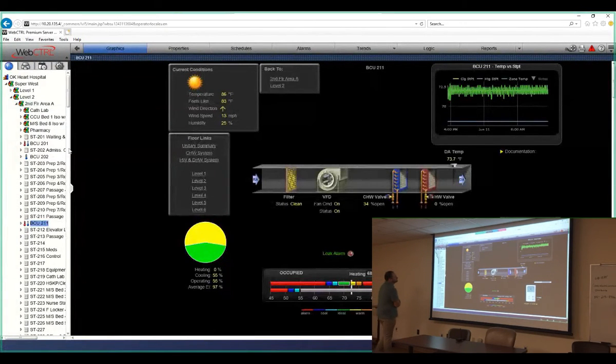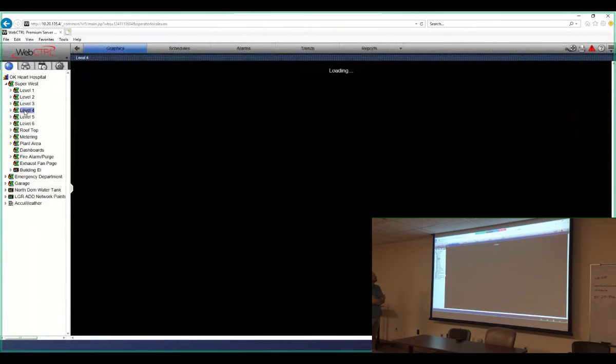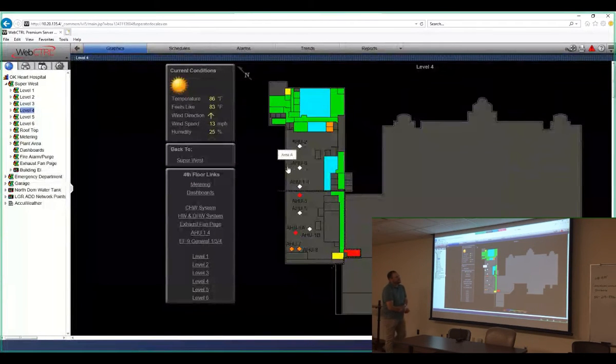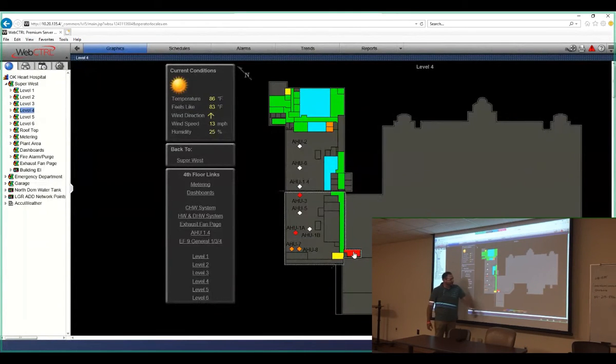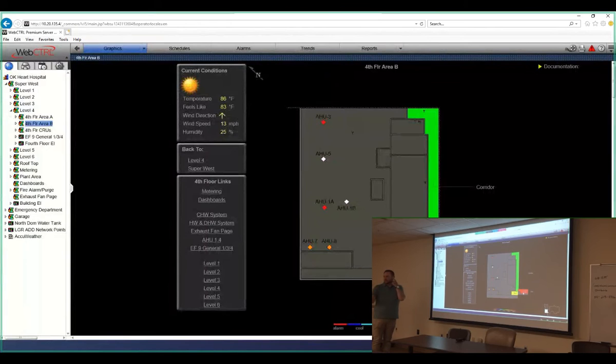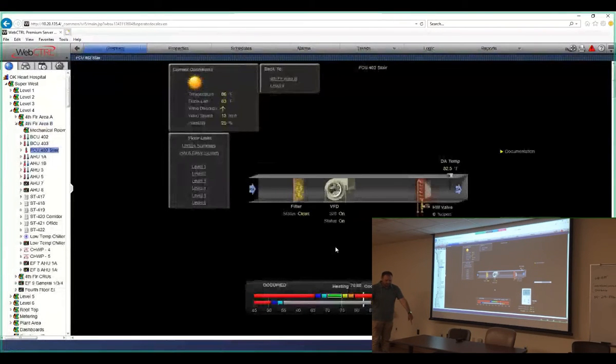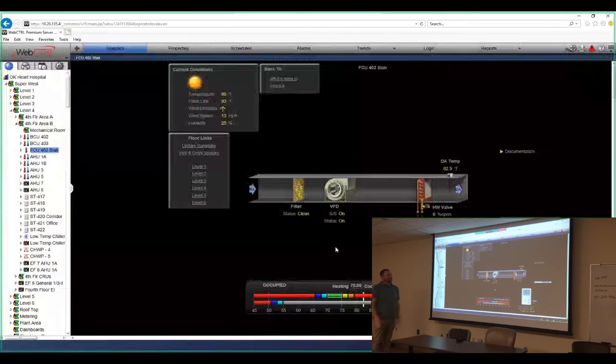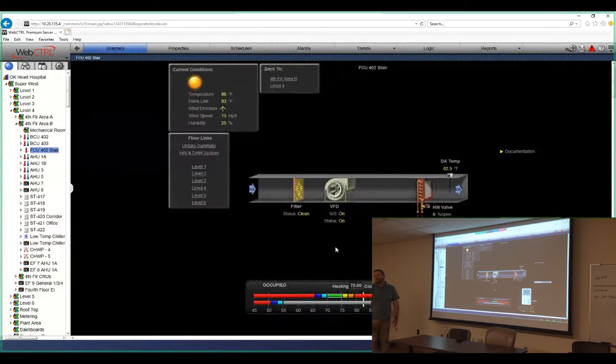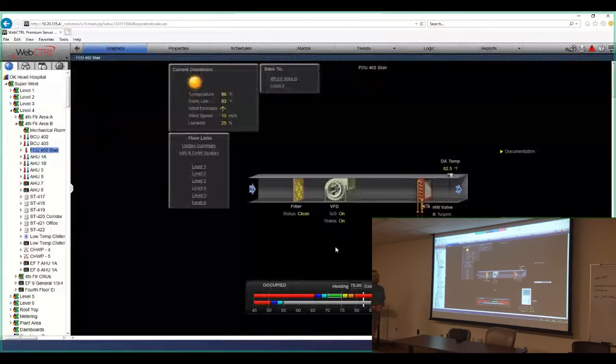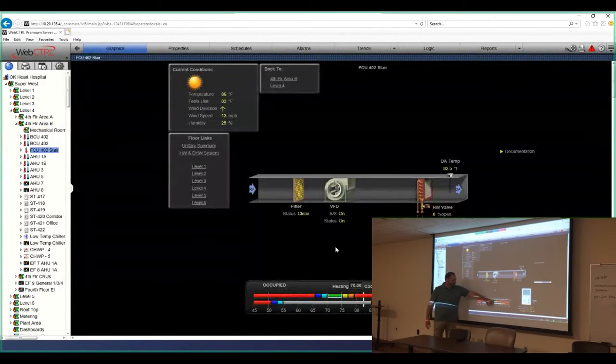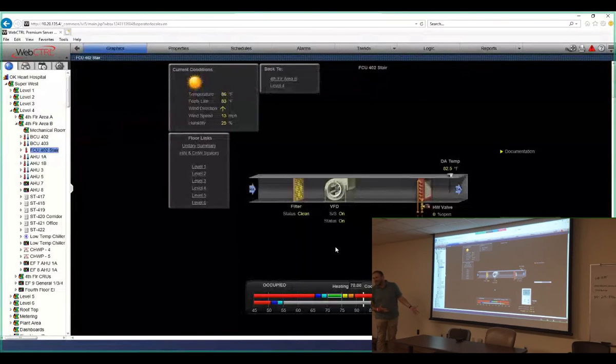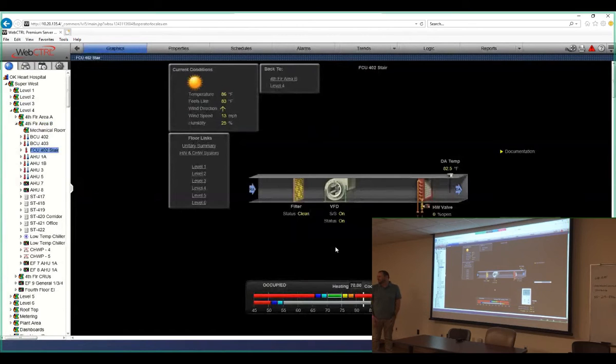So let's go to the 4th floor. If you look at the stairwell here, you've got a fan coil unit right there. So I think there's 4 in the stairwells. You've got 1 on each stairwell on the 1st floor, 1 on each stairwell on the 4th floor. And they're heating only. So that's all they're going to do in the wintertime is make sure that space stays above freezing. So there's probably opportunity to adjust some of these. I don't know what that set point needs to be. Maybe it's 68, maybe it's 65. Maybe you don't want to heat it all the way up to 70. Maybe in the wintertime, about 58 is what we got our others set on. Yeah, maybe it's 58.